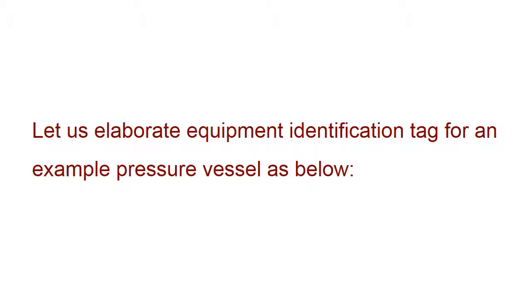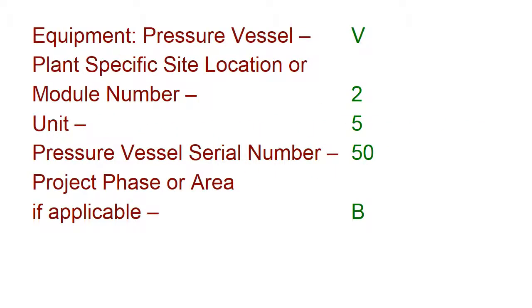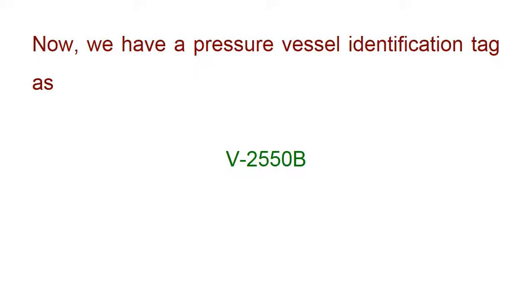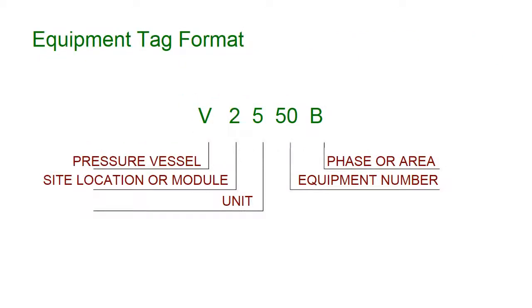Let us review the equipment identification tag for an example pressure vessel. Equipment: Pressure Vessel, Plant Specific Site Location or Module No.: 2, Unit: 5, Pressure Vessel Serial No.: 50, Project Phase or Area if applicable: B. We therefore get a pressure vessel identification tag of V-2550B. The tag format is: V for Pressure Vessel, 2 for Site Location or Module, 5 for Unit, 50 for Equipment Number, B for Phase or Area.